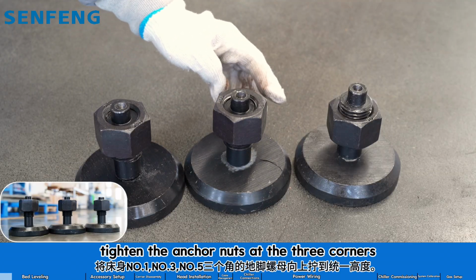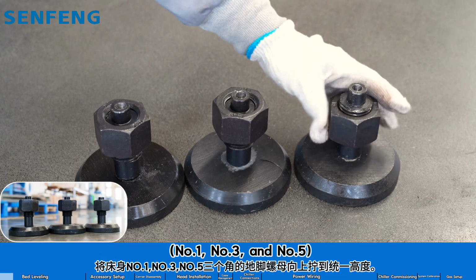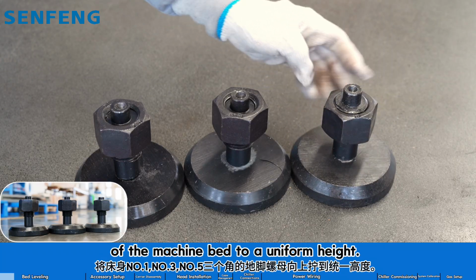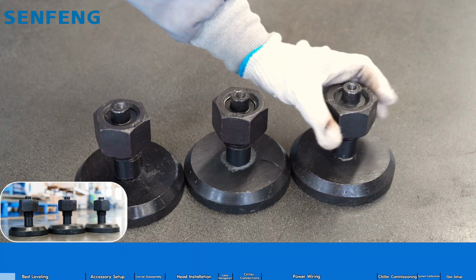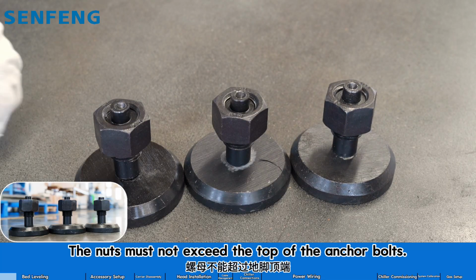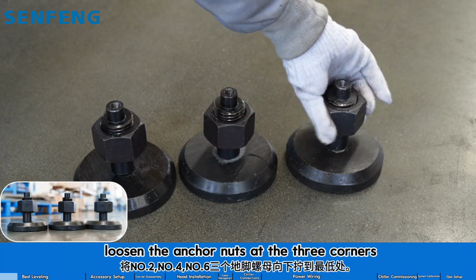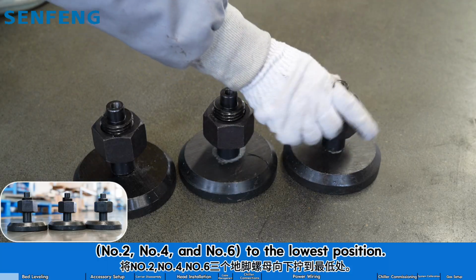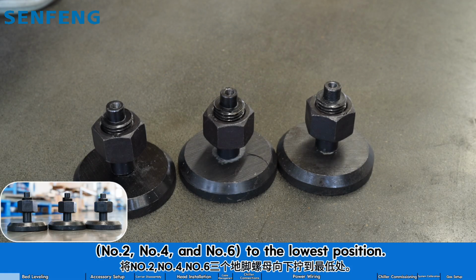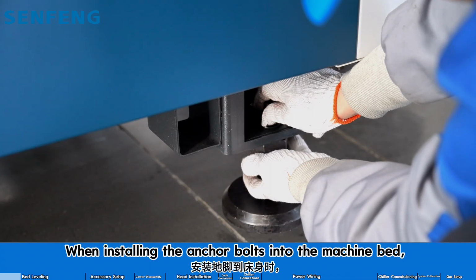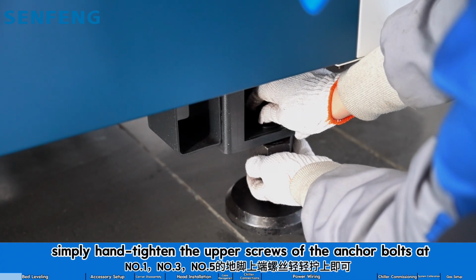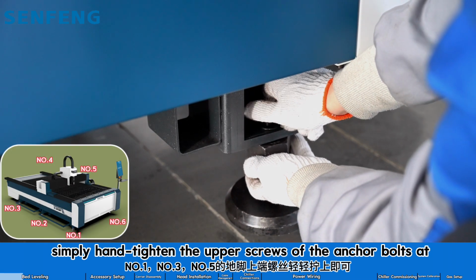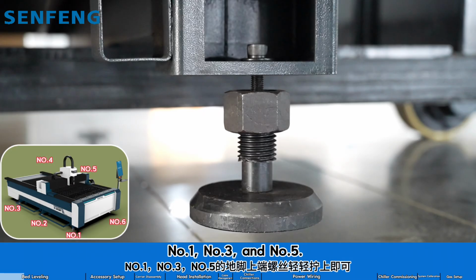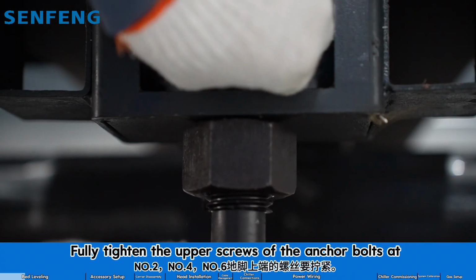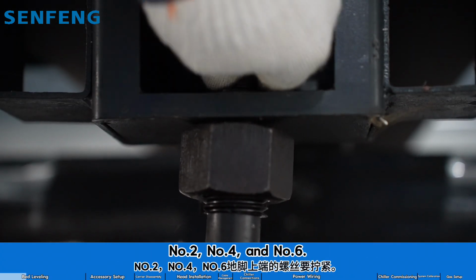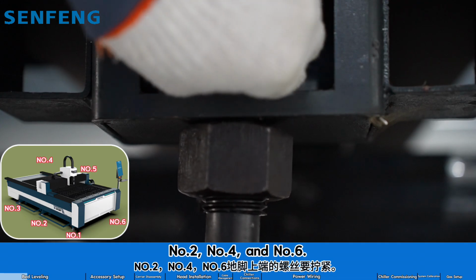First, tighten the anchor nuts at the 3 corners, number 1, number 3, and number 5 of the machine bed to a uniform height. The nuts must not exceed the top of the anchor bolts. Loosen the anchor nuts at the 3 corners, number 2, number 4, and number 6, to the lowest position. When installing the anchor bolts into the machine bed, simply hand tighten the upper screws of the anchor bolts at number 1, number 3, and number 5. Fully tighten the upper screws of the anchor bolts at number 2, number 4, and number 6.